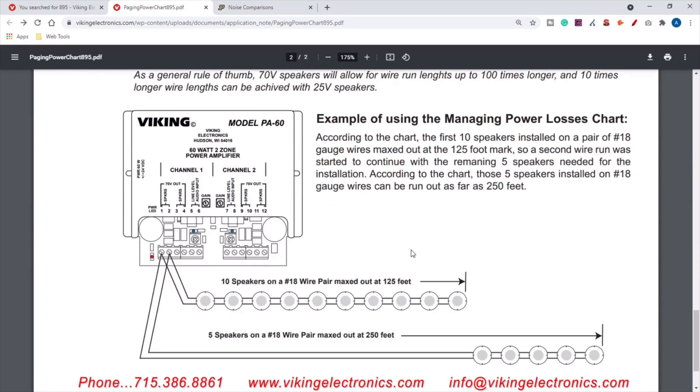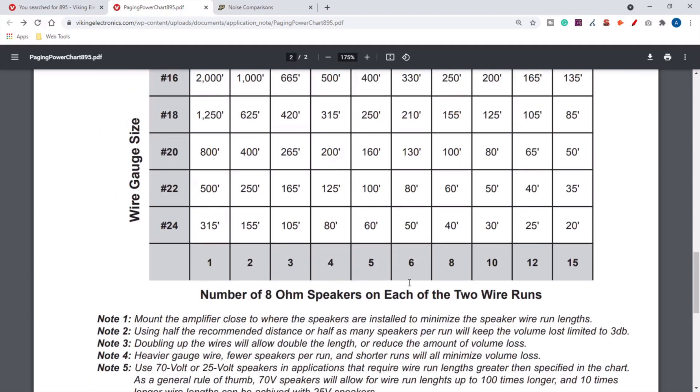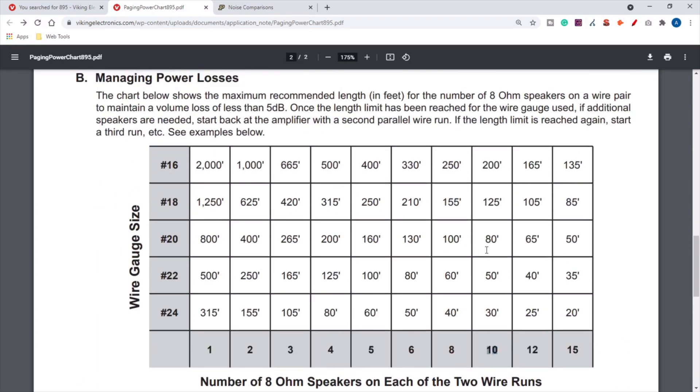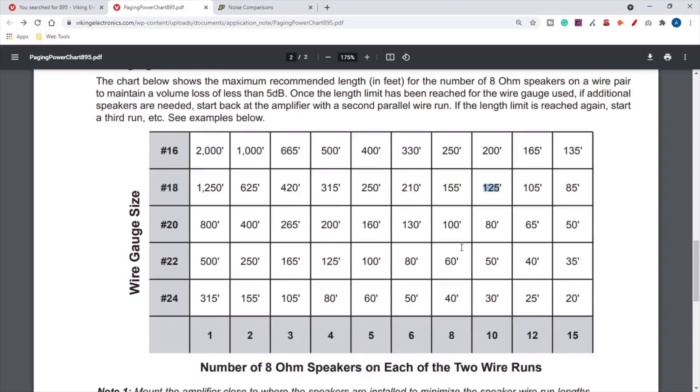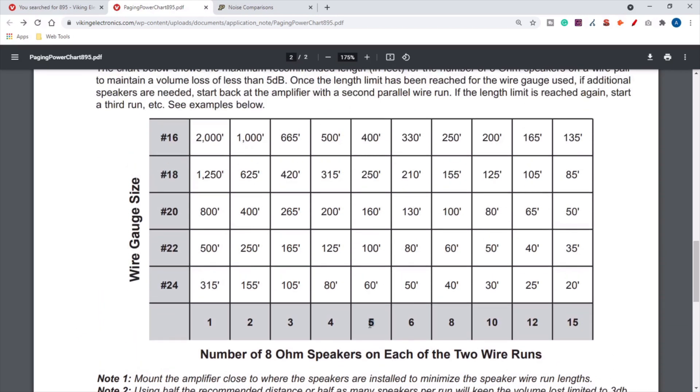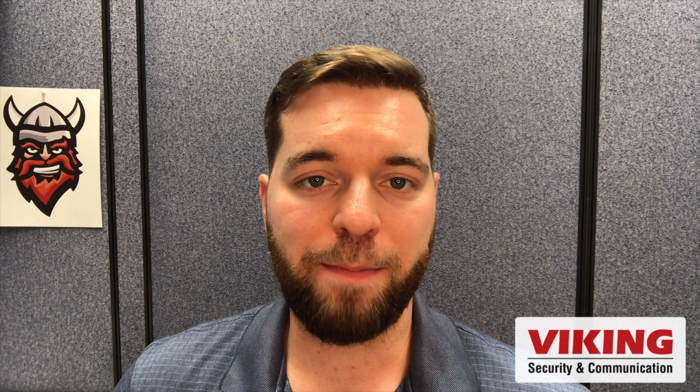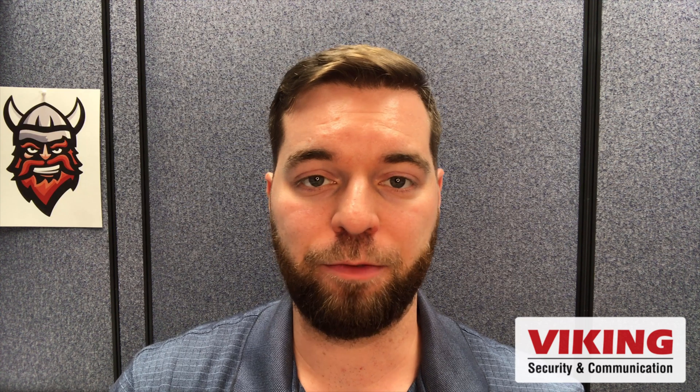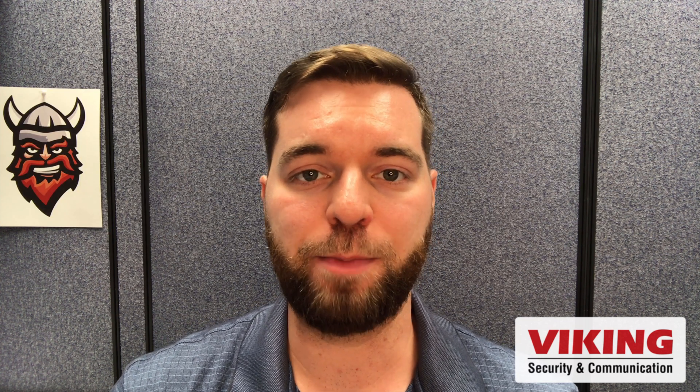If he does need to add more speakers, you can see how the managing power losses chart comes into play. This speaker run on a PA-60 has 10 speakers on an 18-gauge wire maxed out at 125 feet. Now if you've got further speakers, this is five speakers on an 18 pair ran 250 feet, so five speakers, 18-gauge cabling, 250 feet.